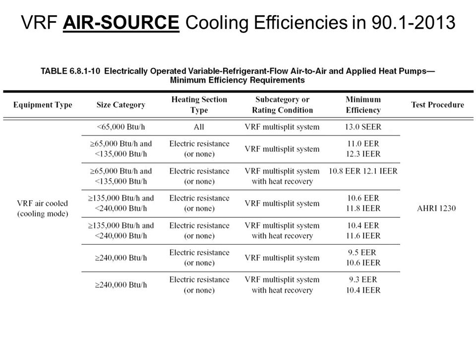Up on the screen, I'm showing you an air source system, right? So no geothermal or cooling tower loop or anything like that, just an air-cooled heat pump. This is an air source system in 90.1 2013. 2010 would have the same data, basically. Actually, it has the same EER and it had slightly lower IEERs. But the IEERs are very easy to hit. When you look at most of the manufacturers' data on AHRI, many of them will just barely hit the EER number, and then almost all of them are going to crush the IEER numbers on this screen.